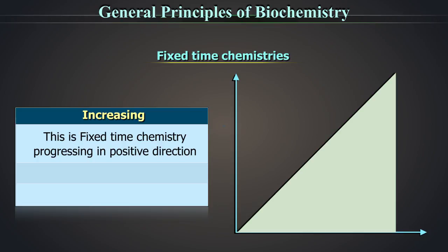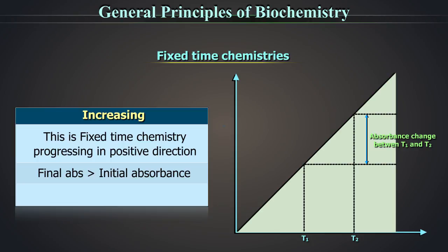Fixed time chemistries could be of two types. A. Increasing type. This is fixed time chemistry progressing in positive direction. The final absorbance is greater than initial absorbance. Therefore, the difference between the final and initial absorbance, called as delta absorbance, is always positive.